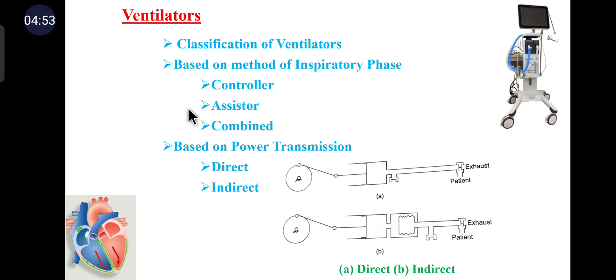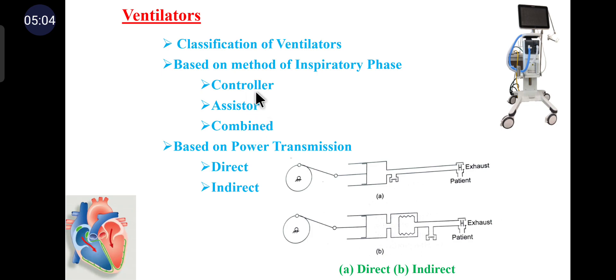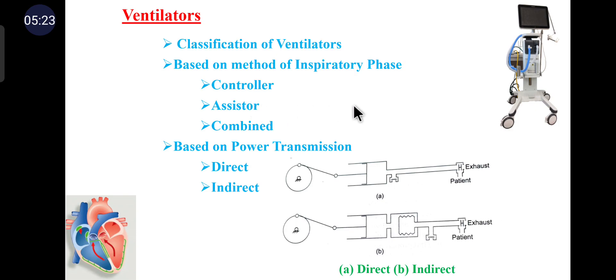In the controller mode, the ventilator operates independent of the patient's inspiratory effort. Inspiration is initiated by a mechanism controlled with respect to time, pressure, or another similar factor. Controlled ventilation is required for patients who are unable to breathe on their own.